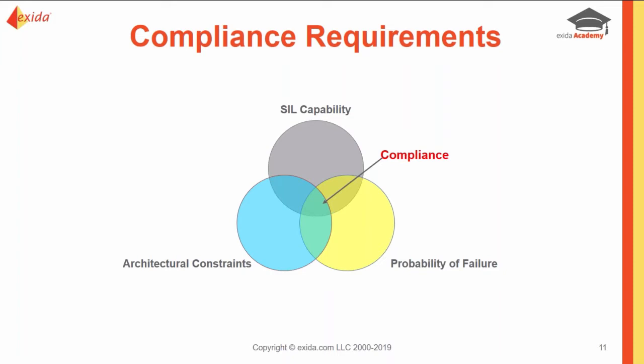The next hurdle or barrier that you need to overcome is going to be your probability of failure. For a device, this means knowing your failure rates from your FMEDA, or your failure mode effect and diagnostic analysis. These failure rates will be published on a certificate, so if you are buying a certified product, you'll already have those there. You can just simply read off the back of the certificate or an FMEDA report.